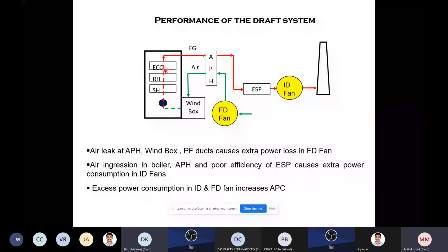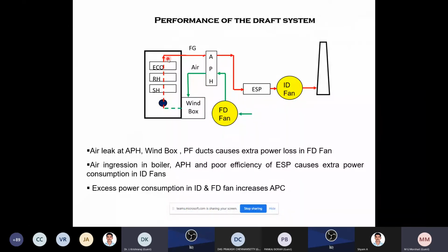Likewise, the boiler should always be operated under vacuum because the flue gas is sucked by the ID fan. The ID fan is much bigger than the FD fan, more or less double. If it is 900 kilowatts, it will be 1800 kilowatts. It sucks the gas, so on the boiler side there will be negative pressure. When there is negative pressure and a leak, air ingress will take place. Ingress in the flue gas path means the ID fan is unnecessarily loaded, and that will consume more power.